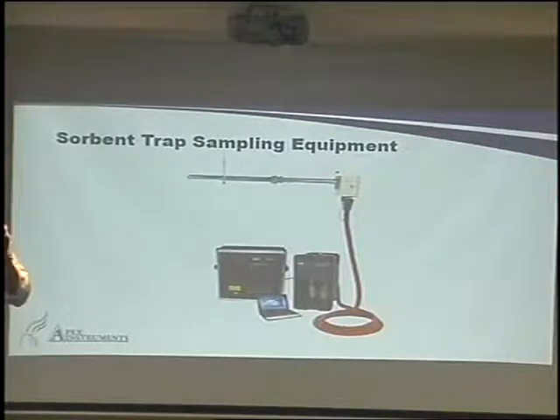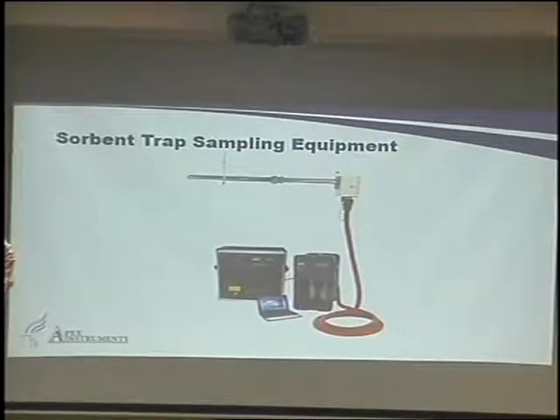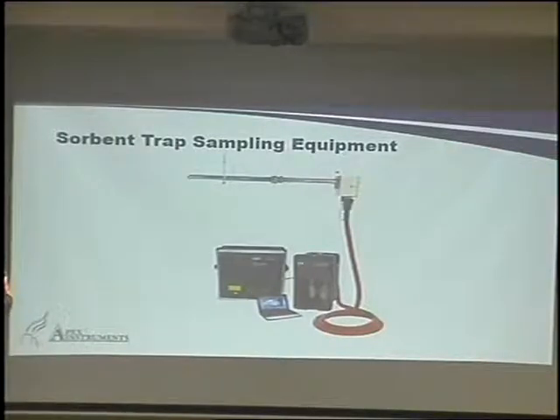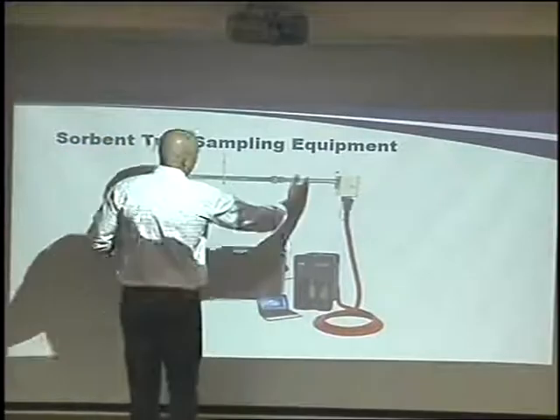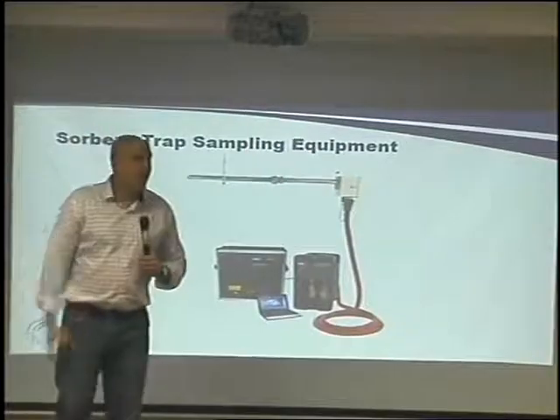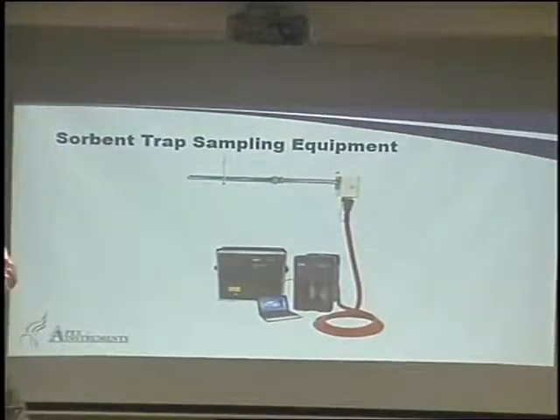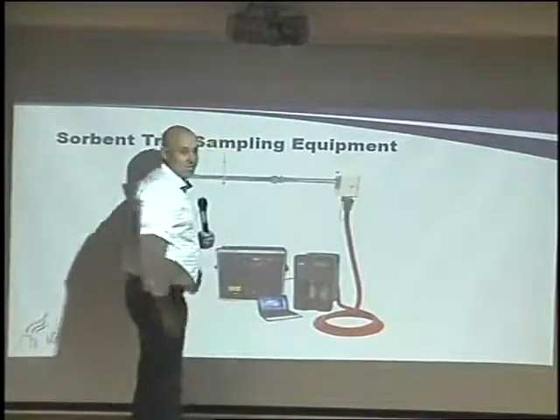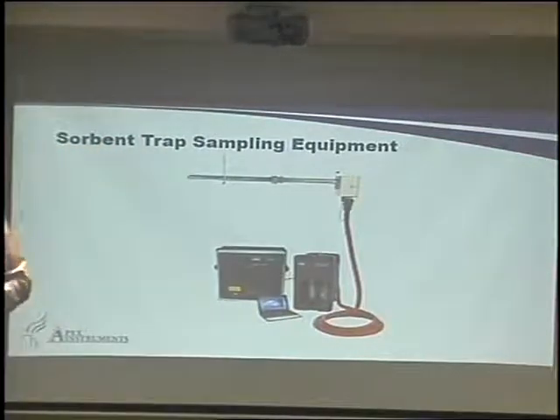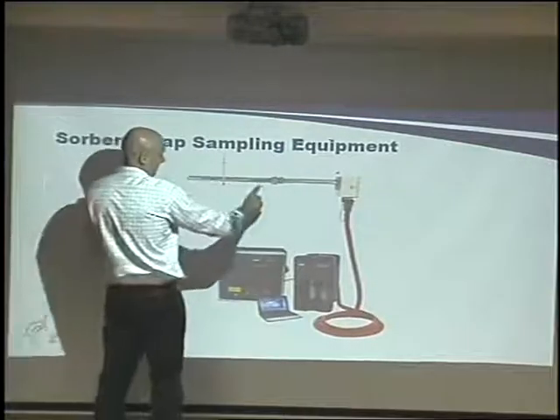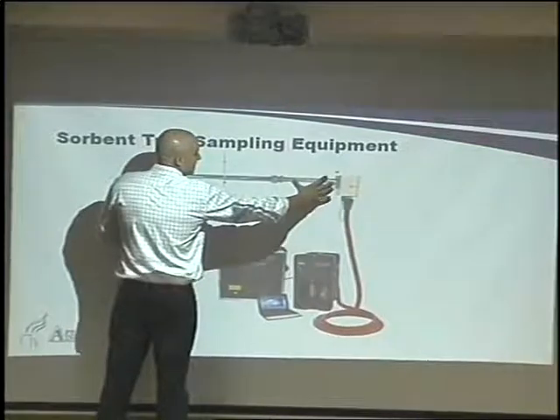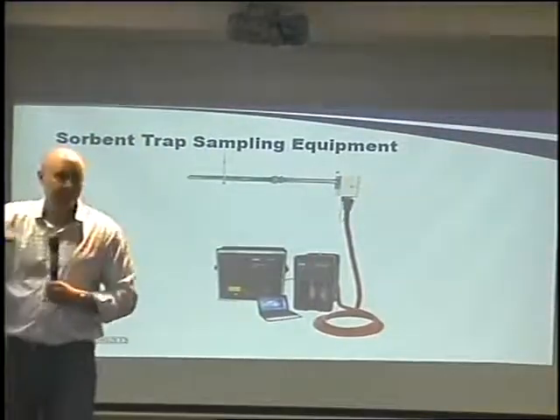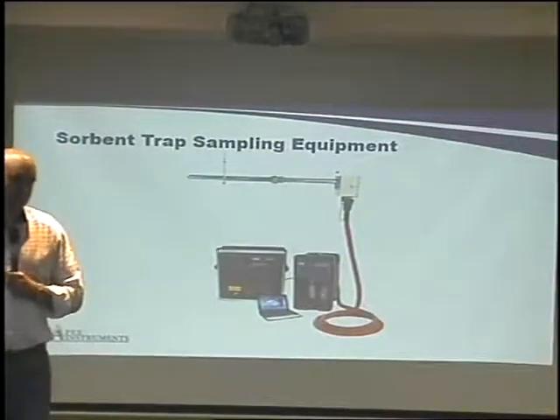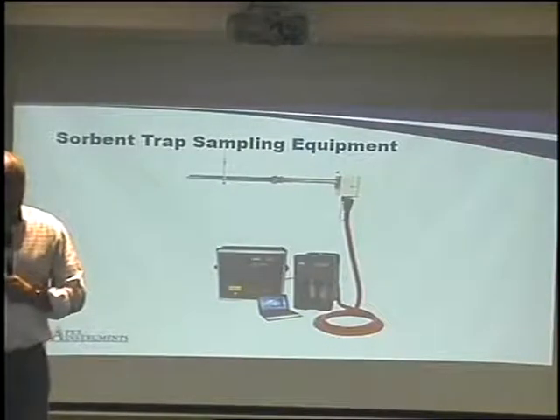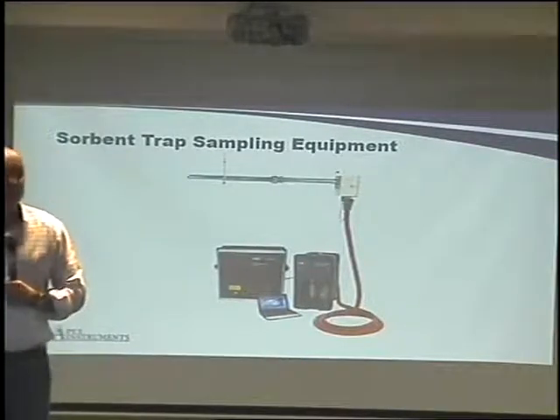We can do dual heaters, maybe not so important here in Thailand. But when we go to places like Chicago or Minnesota in the winter, and it's snowing outside, okay, and this much of the probe is in the stack, and it's 125 degrees, and this section's sitting out in the snow, and it's getting cold, okay? So what we can do is we can actually have one heater here, and it goes to about here, and a second heater in the back that will run independent. So now we can combat the ambient conditions outside, okay? So the back heater might run hotter than the stack heater because it's 0 degrees outside.